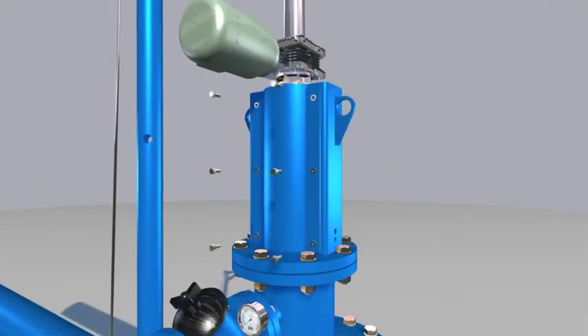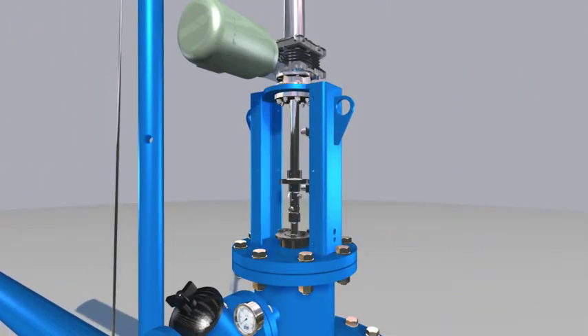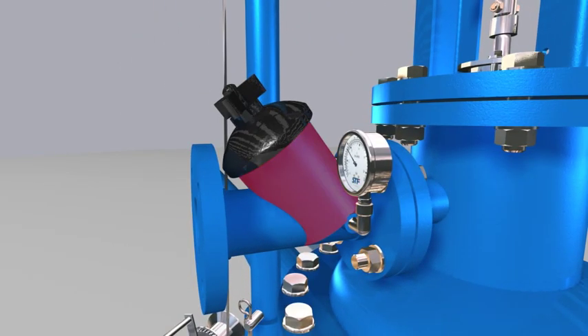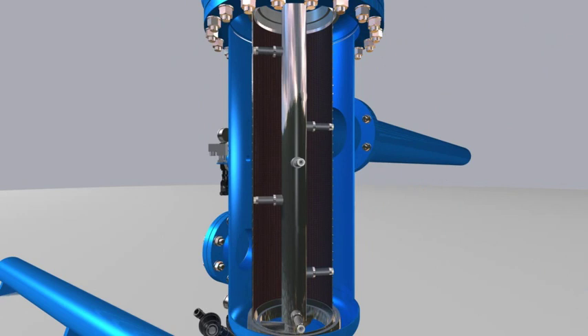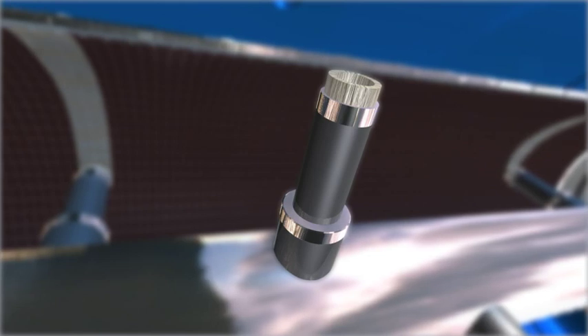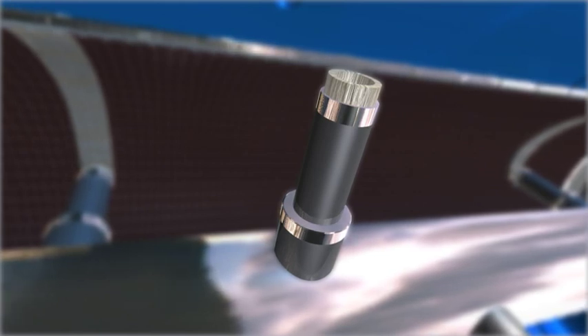When this value is reached, the differential pressure acts on the control panel that commands the opening of the drain valve, which is housed in the cleaning chamber, and the helical motion of the suction scanner, where the suction nozzles with nylon bristles, patented by STF Filtros, are housed.